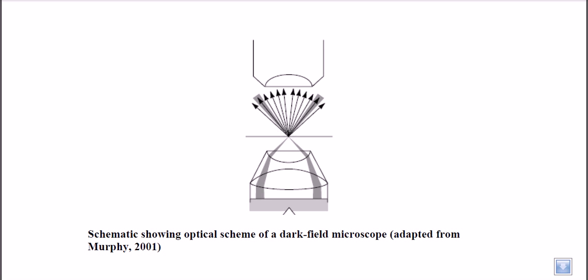Now, when you place a specimen on the slide, the peripheral beam passes through the specimen. According to the density of the specimen, light is diffracted in different ways. Some of those beams are diffracted inward and collected by the objective lens. The objective collects those diffracted beams, allowing us to observe the specimen as bright light against the dark background, while areas of the slide with no specimen remain dark.